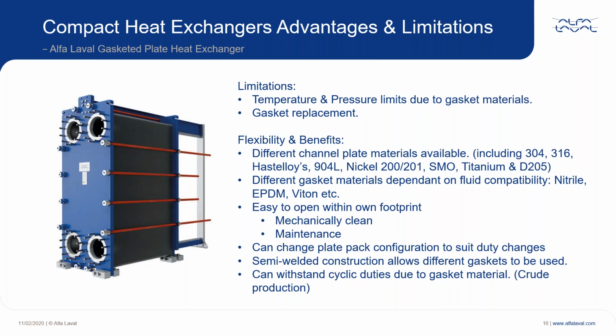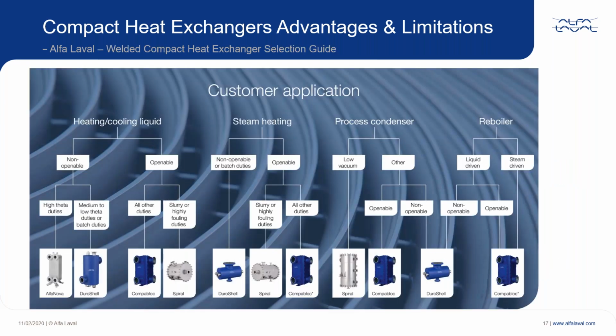The flexibility and benefits: you can have many different plate materials, 304 and 316 for HVAC duties, all the way up to titanium and D205 for process duties. Okay. The other heat exchangers in our range can be considered as welded. Now, which one you choose depends on your duty and whether you're liquid or condensing, and also whether the unit needs opening for mechanical cleaning. Many of our units are sealed and can only be cleaned by chemical methods.